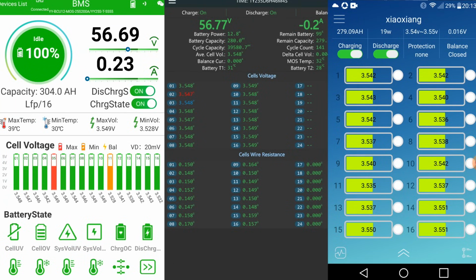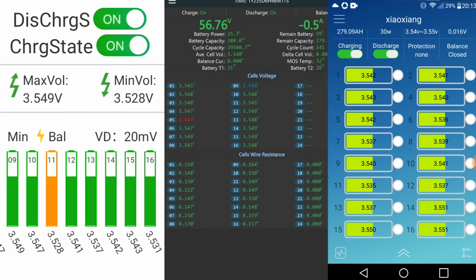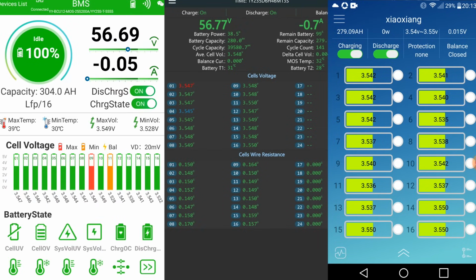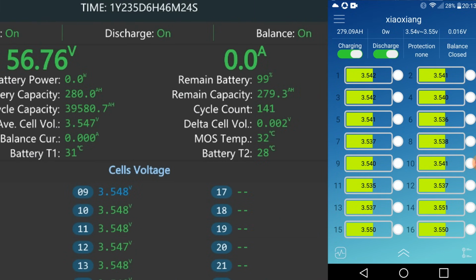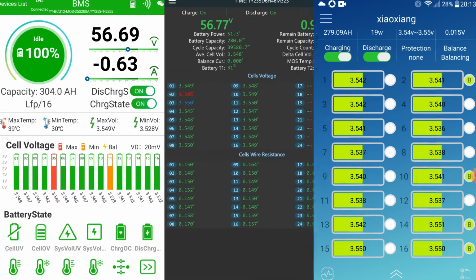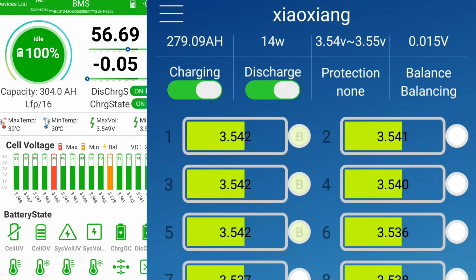So let's have a look at the BMSs, what's going on. Here we have all 3 BMSs again. On the left, the Heltec BMS in the top battery shelf is now down to 20 millivolt, at 56.8 volts or 57, whatever. Balancing has completely stopped because the deviation is so small now. The JK in the middle is down to 2 millivolt deviation. That is incredible, balancing has stopped here as well because we are under the threshold. And the overkill BMS in the bottom shelf, deviation is 15 millivolt.